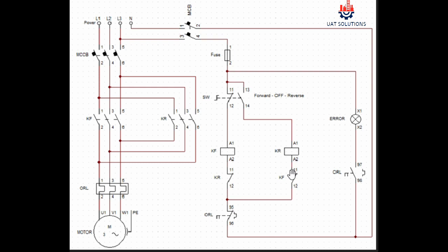This is called electrical interlocking and it is used to prevent the two contactors from energizing at the same time. If contactor KF is energized, KR cannot be powered because the circuit is open at KF 11 and 12. Same goes for the contactor KR.